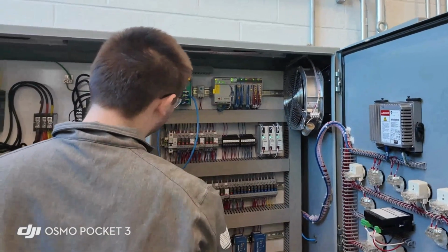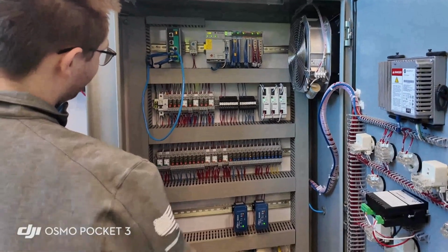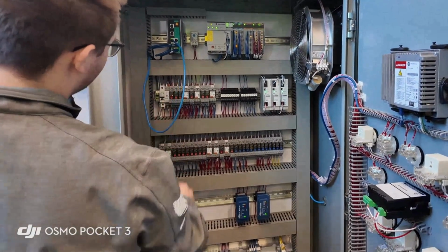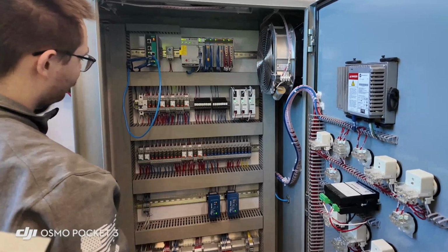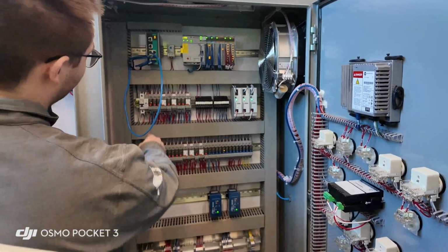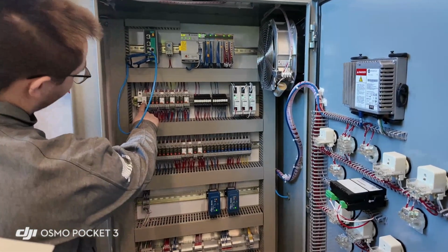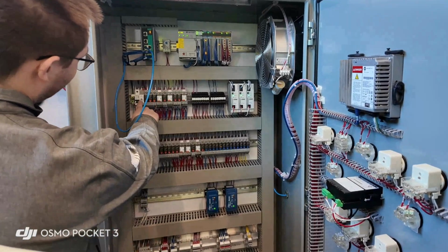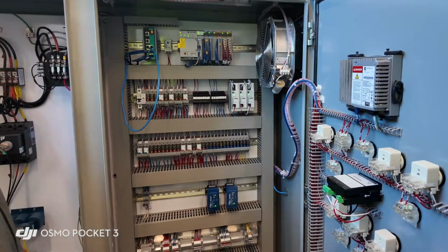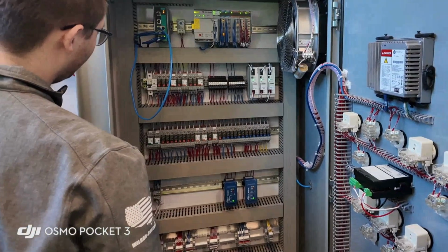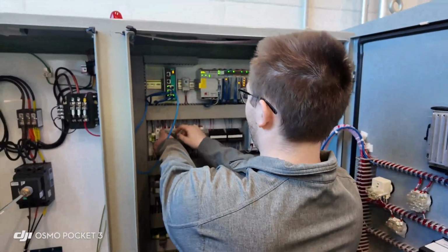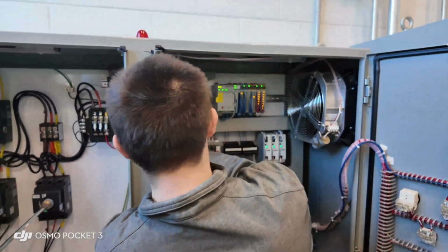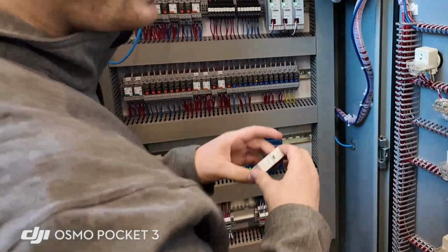Second row down, we have our control power coming in, and it's protected by a circuit breaker and a surge suppressant device. If there's ever a surge inside the panel, this will trip. It's green, and if you ever see a little orange tab in here, that means there was a surge, and you'd also get an alarm on the HMI. How do you reset that? They're hot swappable, so if there's a power surge, you have to replace it. Part number right down there, and this is just Phoenix Contact.